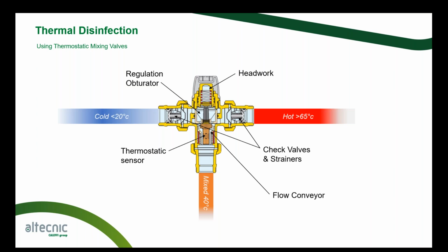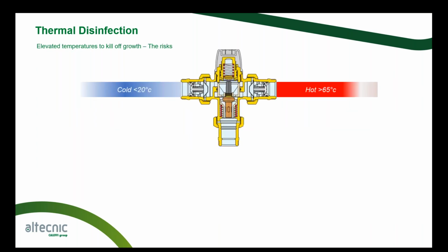There's nothing electronic there. There's nothing massively complicated. It is the fact of two springs and a thermostatic element which moves up and down to close and open the different hot and cold armatures to make sure we get a blended mixed temperature.